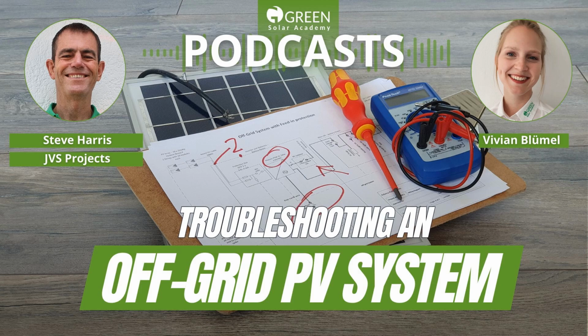So if you've had repeated low voltages switching off the inverter because you've taken your battery to the limit every time and you're relying on the inverter to switch off on low battery, it's almost like the systems develop a fault because you've taken them onto their own limits, and then they just say, we can't take it anymore. Another common thing is that people push the boundaries where there's an integrated MPPT charger in the inverters, and it's another big failure, especially for MPPT charge controllers, is people put over voltage on the charge controller and it fails. And so they go, oh, my batteries aren't charging. Well, your charge controller has failed because you've put too many volts on it. You've put too many panels in there because you're working right on the edge of the parameters of the charge controller.